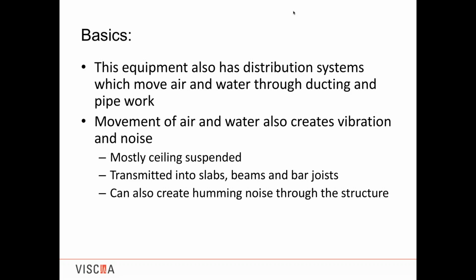You'll typically, mostly though, it will be in the ceiling suspended equipment and the rigid mounted equipment to the base, but also the humming noise that you would get. Sometimes you won't feel the vibration, but you'll hear a sound, and that sound will be coming from vibrations where the equipment distribution system is rigidly touching some building structure.